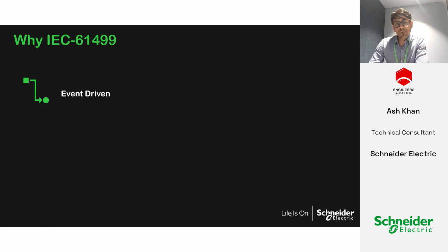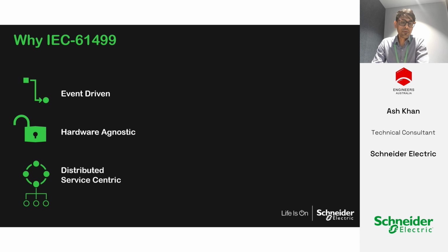So what's with 61499? It moves away from cyclic scan - it's event-driven logic. It does do a cyclic scan of the IO, but the actual logic isn't executed on every scan. It's exception-based, meaning if something has changed, then the event or logic is executed. It's also hardware-agnostic, decoupling itself from software and hardware lock. Thirdly, it's distributed or service-centric deployment - it no longer starts with a device-centric implementation, but looks at the process as a whole.